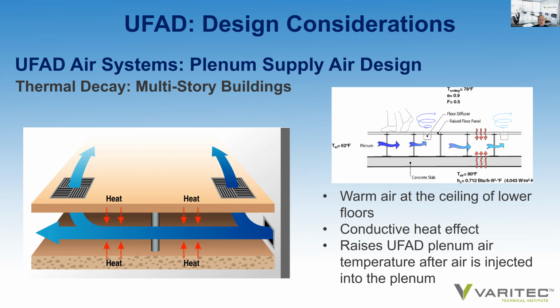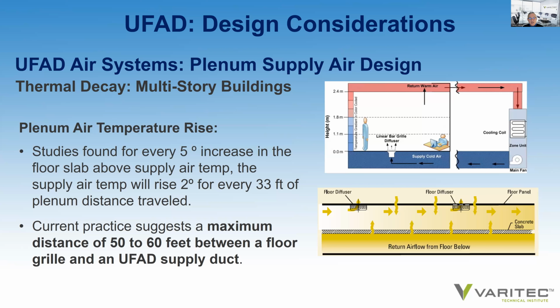And this resulted in some troubled UFAD projects in the early days, because thermostats would regulate diffusers to meet the perimeter load, causing overcooling to occur in the interior zones of a space. So that conductive heat effect has to be addressed. Studies have found that for every 5-degree increase in the floor slab above supply air temperature, the supply air temp will rise 2 degrees for every 33 feet of plenum distance traveled.